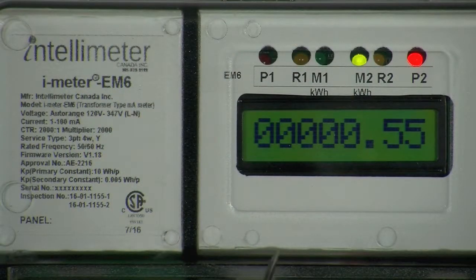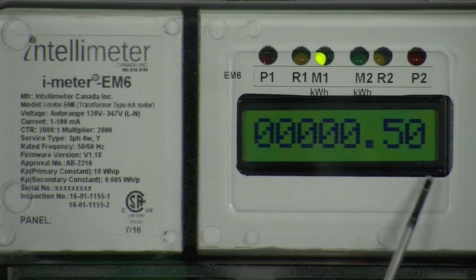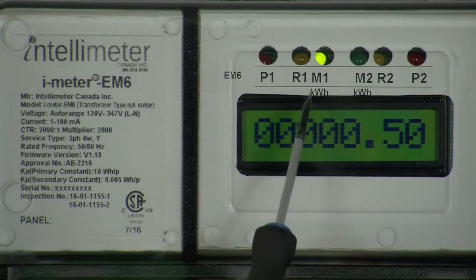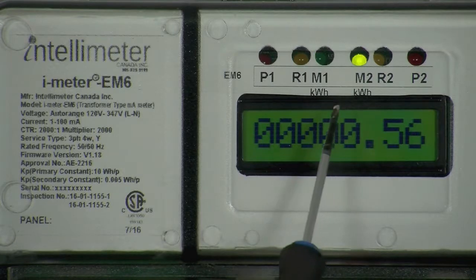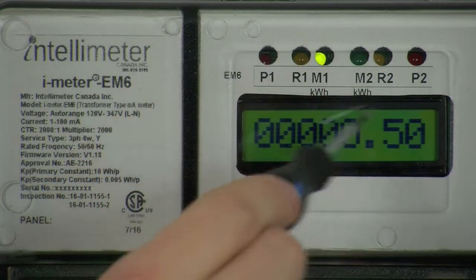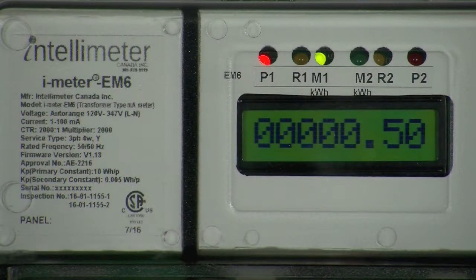As you can see, the iMeter EM6 is now powered up and we have information showing on the display. The display cycles between kilowatt hours for meter 1 and kilowatt hours for meter 2. From a troubleshooting standpoint, we are mainly concerned with the LEDs located above the display. In order to perform proper troubleshooting, we must first put load on the circuit, breaker, or feeds that we are metering. Any load above 1 amp per phase should suffice.